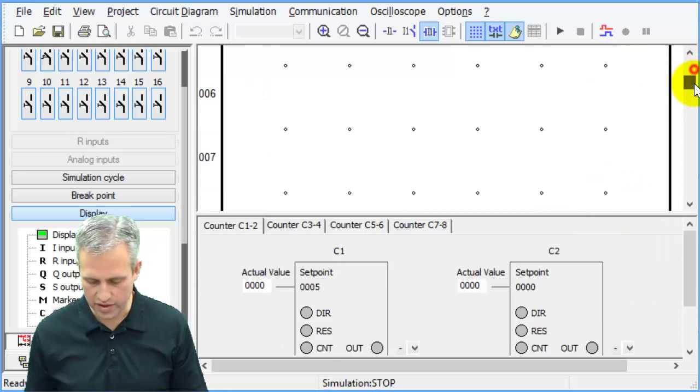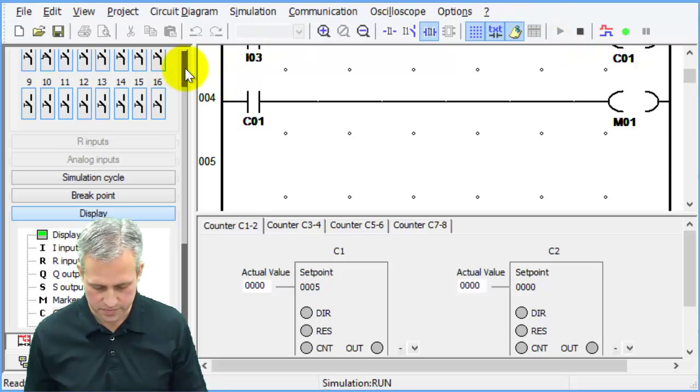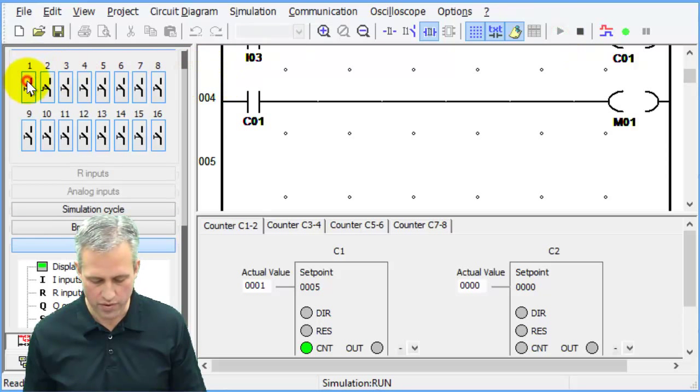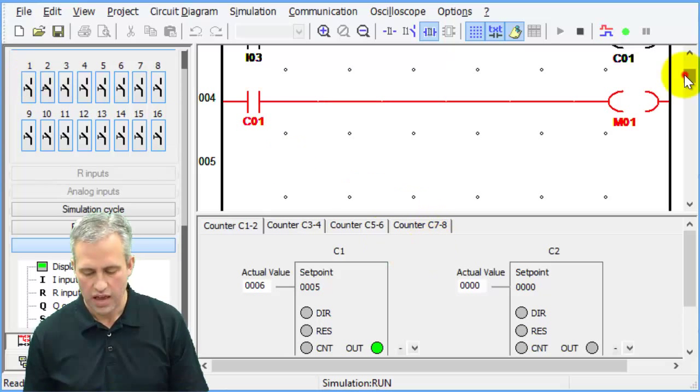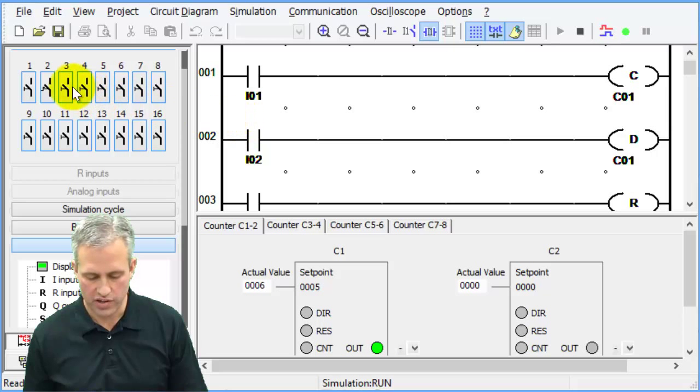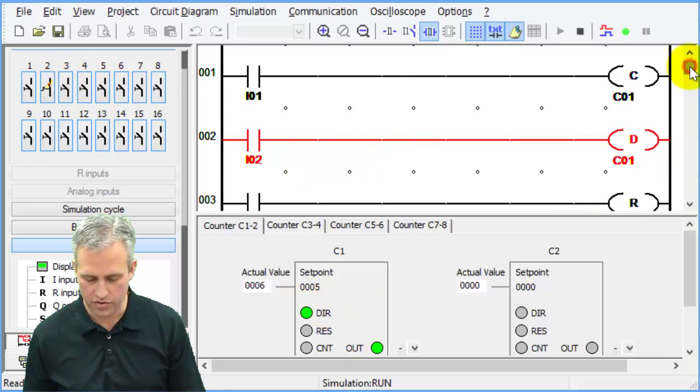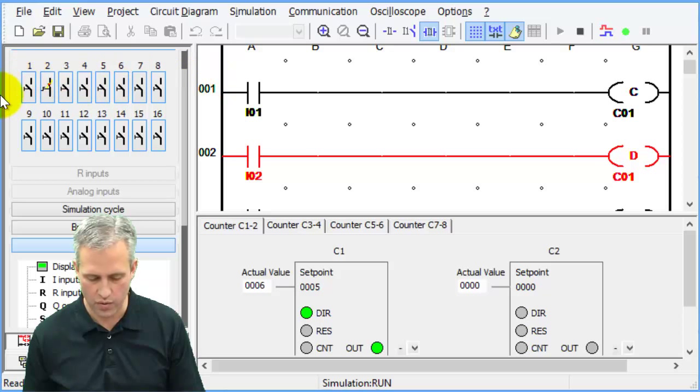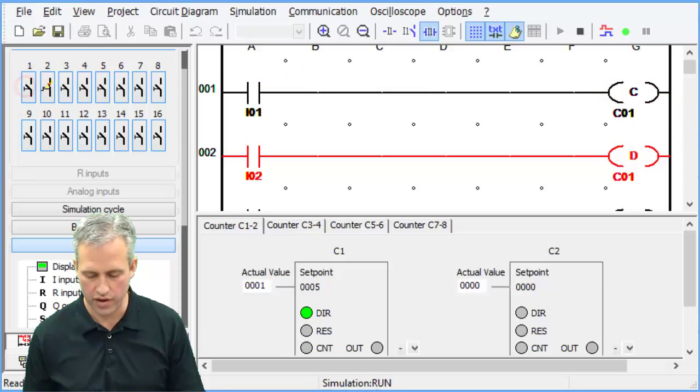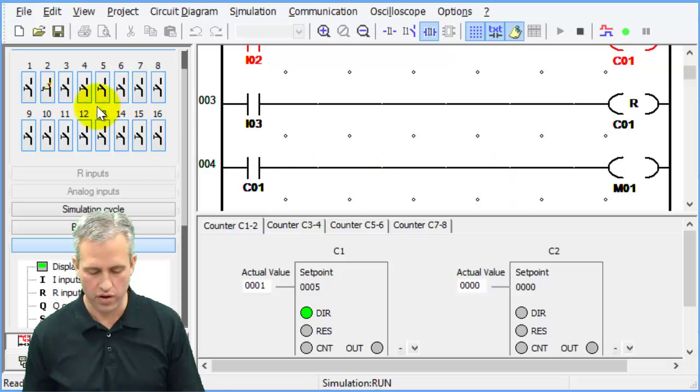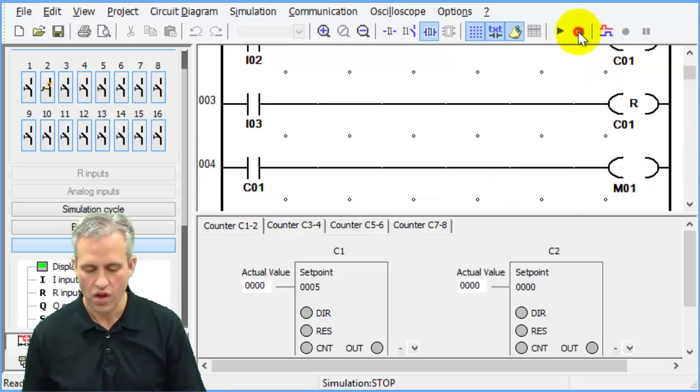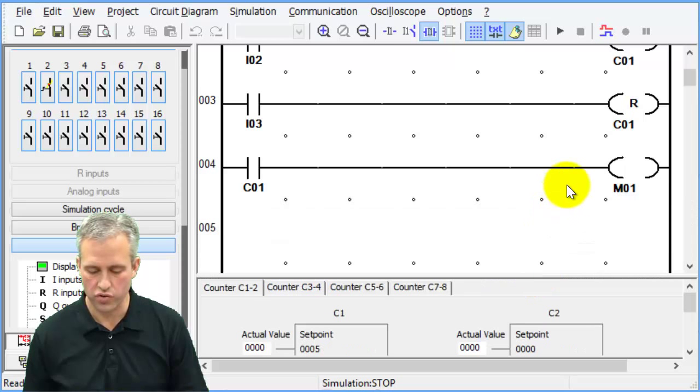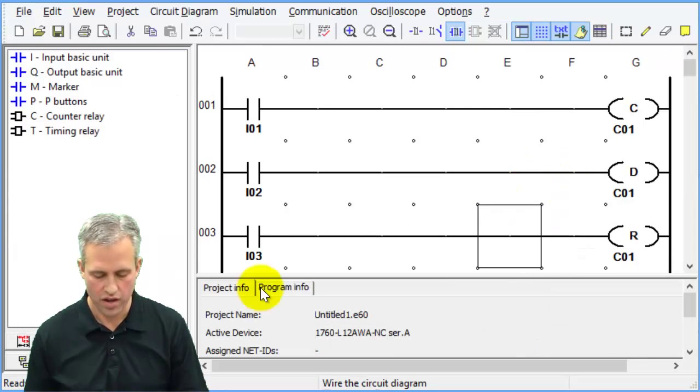And what I want to do is I just want to show you the ability to change your counting direction. Guess what it does, but you can't possibly guess. So if I hit I1 right now, it counts up, three, four, five. I can even go over if I wanted to. I could switch the direction, so I can hit I2. Now I'm going to be going the other direction. So now when I hit I1, it's going to be counting down. So there it's five, four, three, two, one. You can see that once I got below the threshold it went off, and you can also reset it, which just snaps it to zero. So direction just lets you set whether you're counting up or counting down.